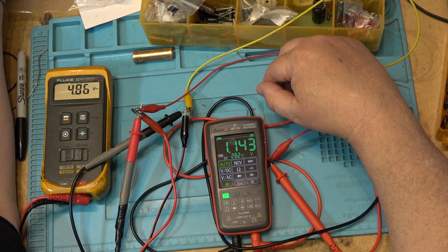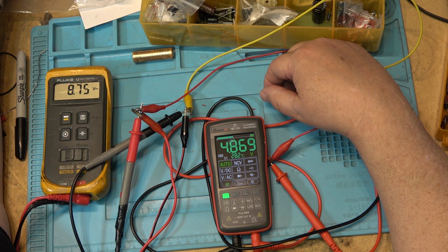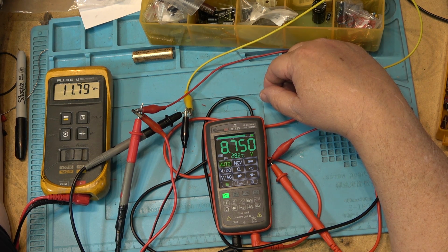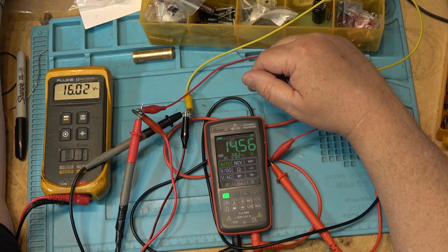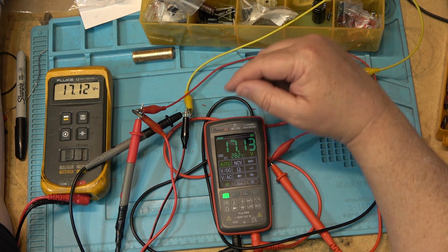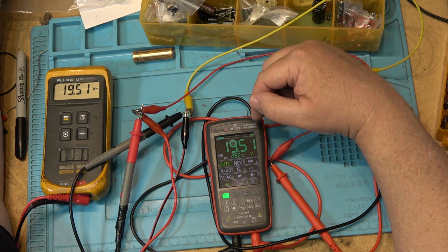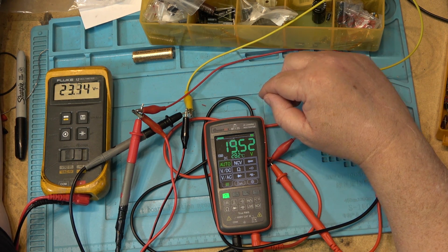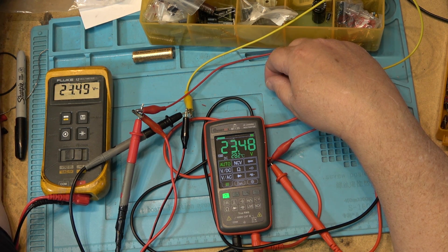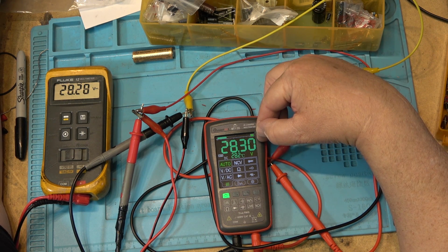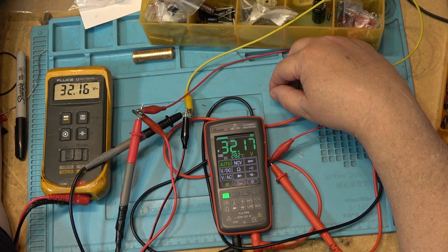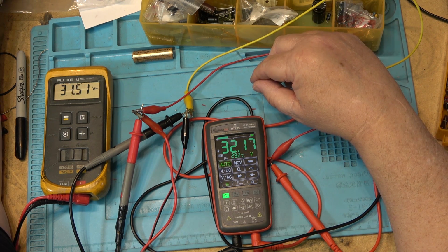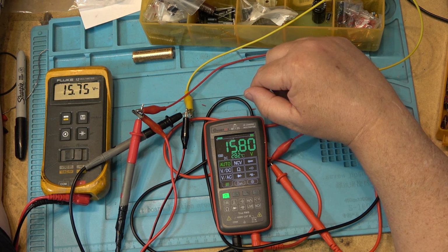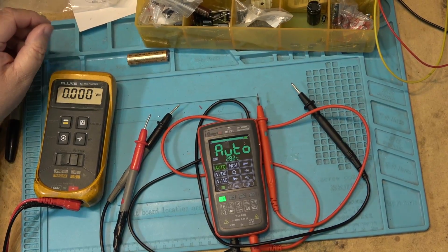And as I ramp up the voltage, 4.86, 8.7, 11.8, 14.5, both tracking exactly, 17.13 and 17.12. We're splitting hairs here, 19.51, 23.4, 28.2, and the maximum that my power supply can go, 32.17, 32.16. Close enough. It's accurate. It will be a Fluke or a Mustool if it's accurate, I guess. That's a pass. We'll check some transistors.